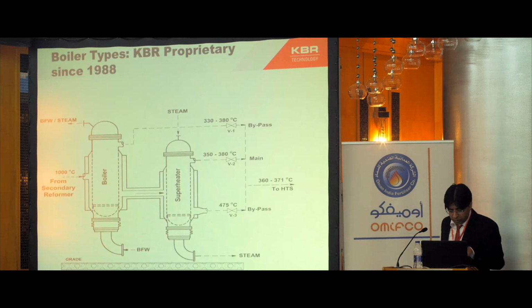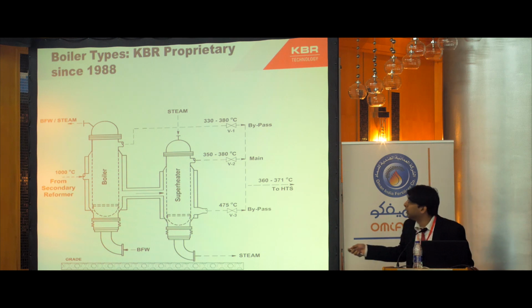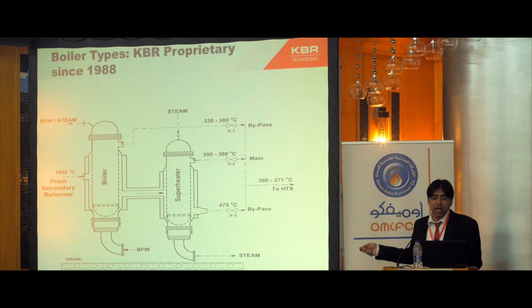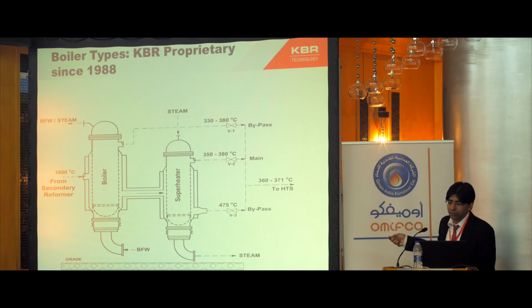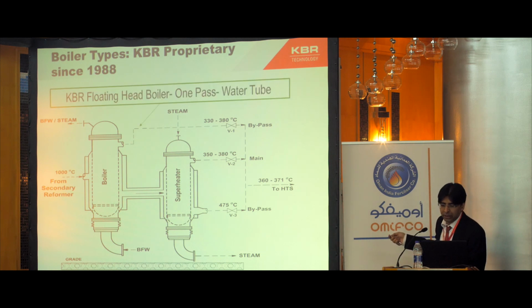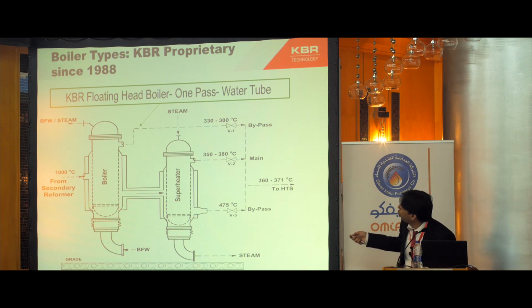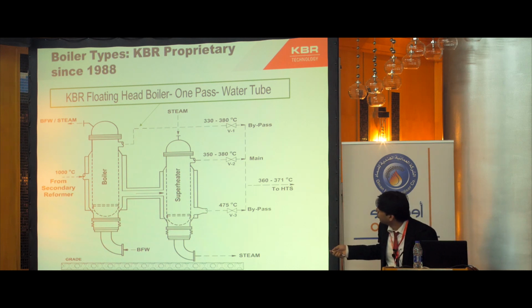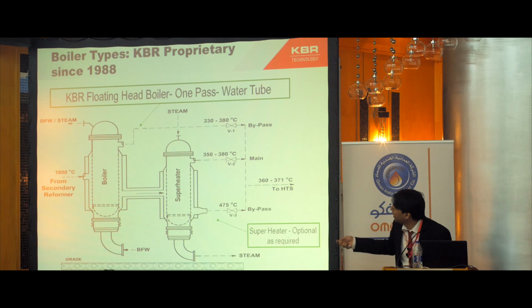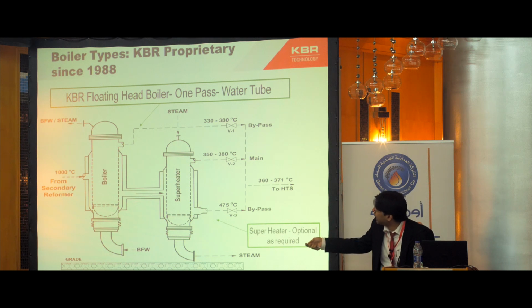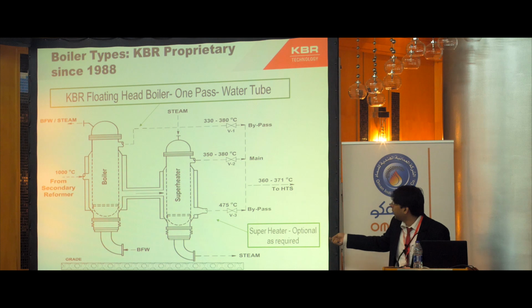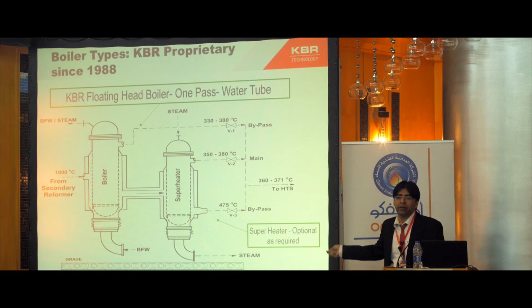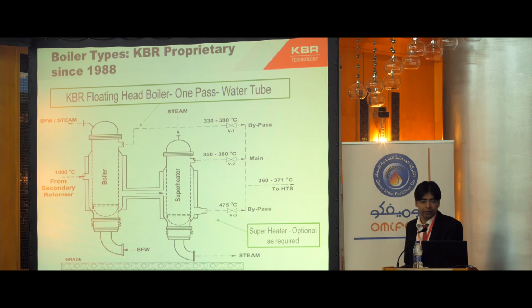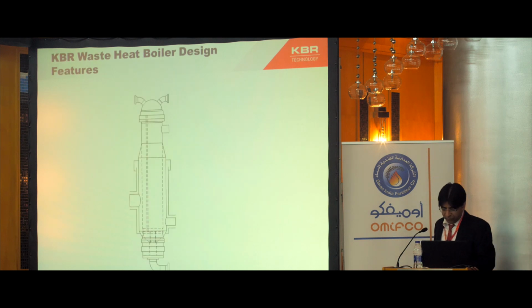Now, after 1988, we designed this floating head design. Seeing the issues with the MWK bayonet design, we invented this new design for the waste heat boiler, which is the KBR floating head boiler with one pass water tube. The superheater is also a quite similar design to the waste heat boiler, but it is optional and can be used if required. Now coming to the features of this new waste heat boiler.